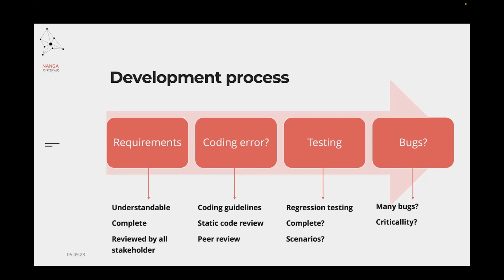So the development process, in case of a Class B device, if well documented in the risk management or software development plan, might reduce P1 related to the process to 1%. In case of Class C, it can be even 0.1%. The claimed level of reduction is up to you, but you can develop and document it as a pre-process value in the risk management or software development plan, and then this level of reduction can be applied to all software risks.